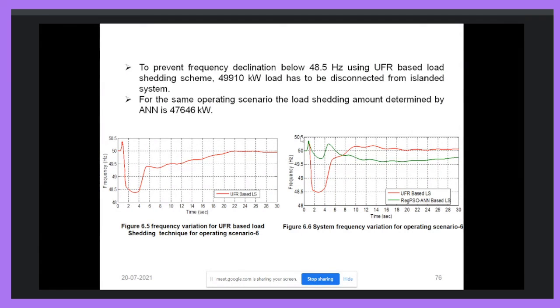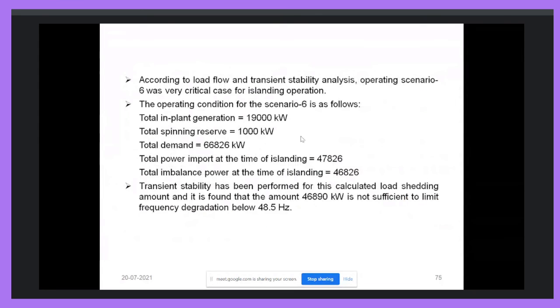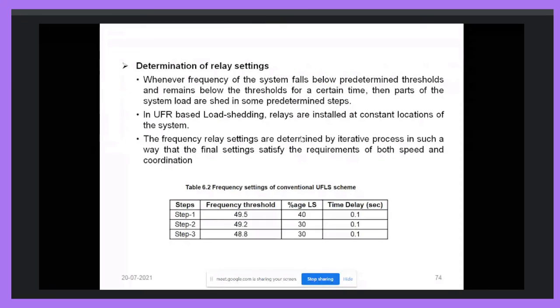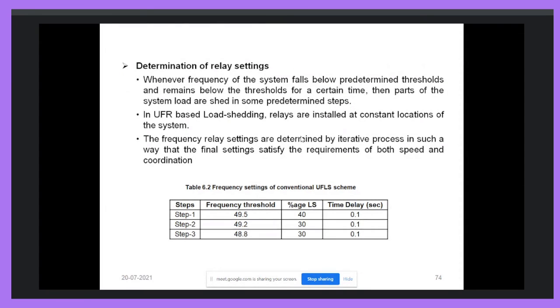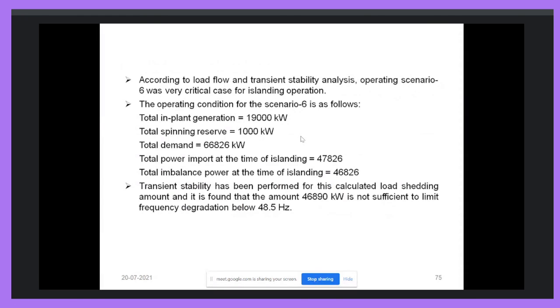In the case of artificial neural network based load shedding, the frequency deviation is very low and accurate. If we use under frequency relay based load shedding, then what will happen? The relay will wait until the frequency reaches the particular value which is set in the relay. Suppose we set 49.2 hertz in the relay, then until the frequency reaches 49.2 hertz, step 2 will not be activated. The relay will wait till 49.2 hertz frequency and it will further wait for 1 second because of the time delay which is provided. Then only step 2 will be activated and load shedding will be initiated. So in this case, the frequency will go down to 48.5 hertz.